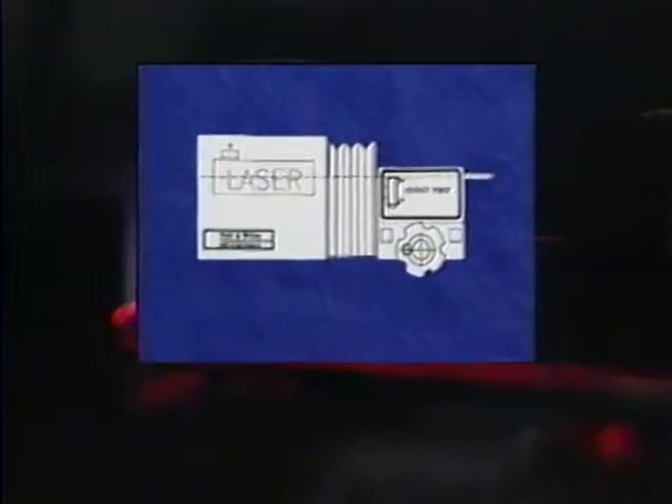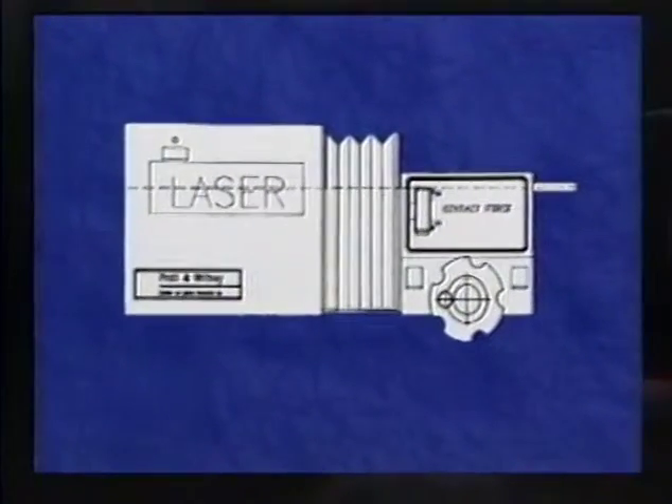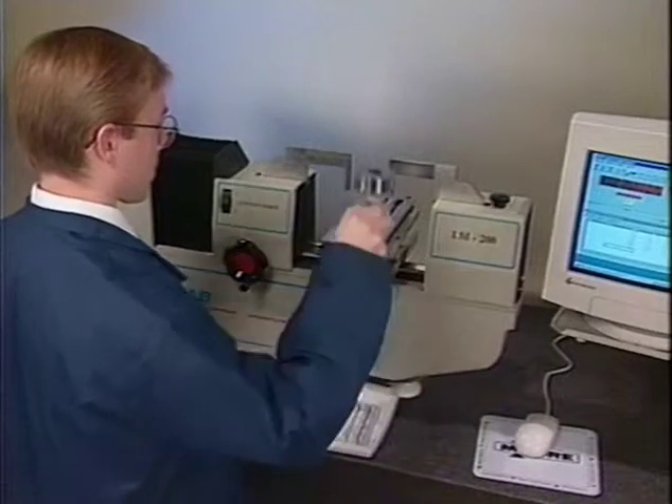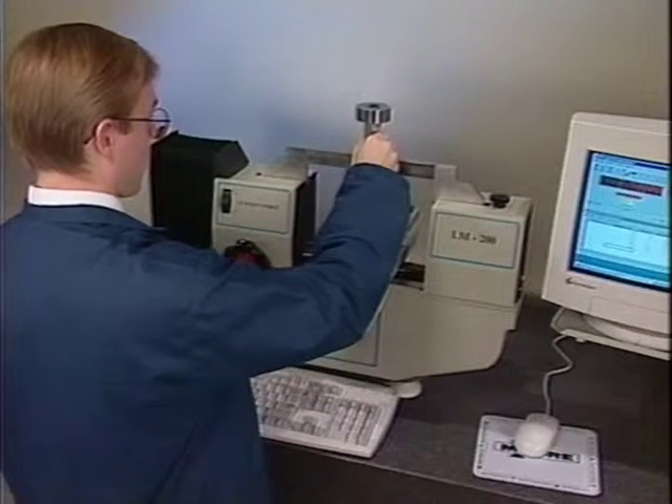The laser path is in line with the measurement axis to eliminate Abbe error. Because this wavelength of light is stable, linear, and has very high resolution when compared to like instruments, LaserMike can provide an extremely accurate method of measuring linear dimensions.